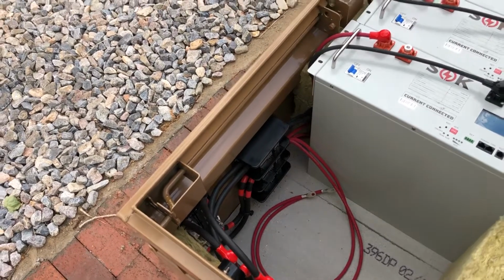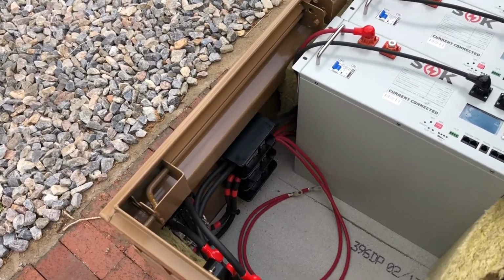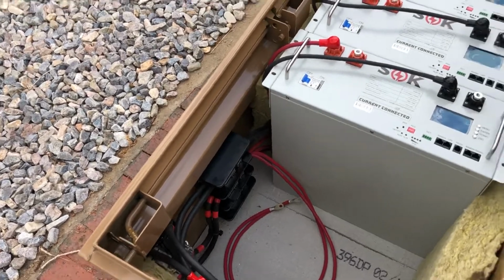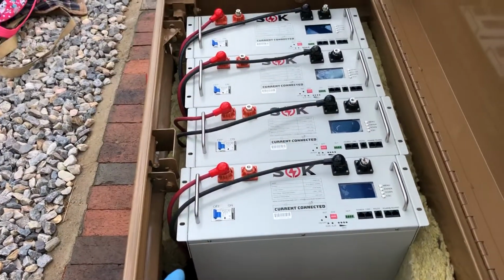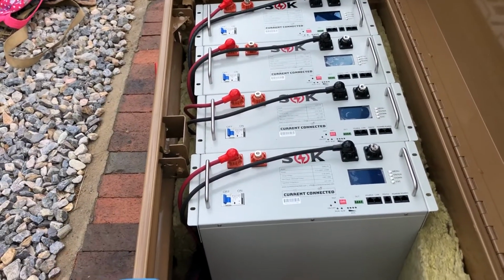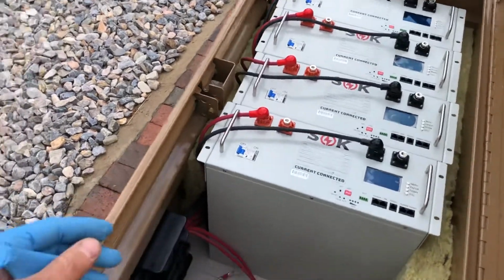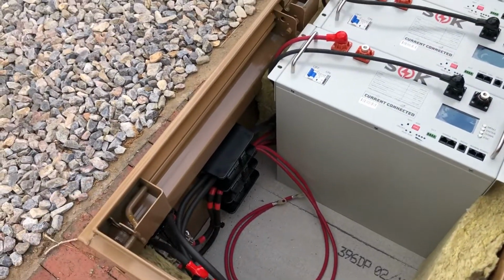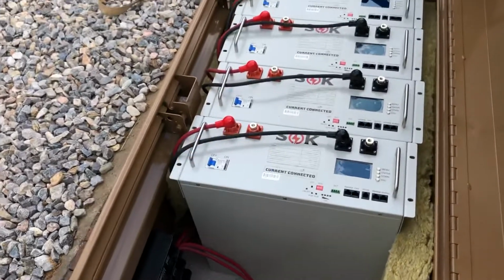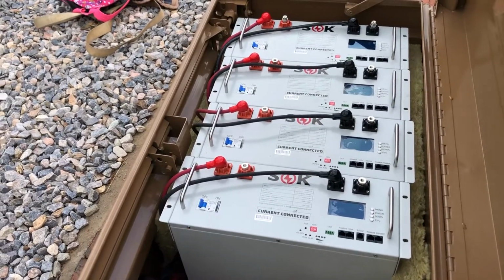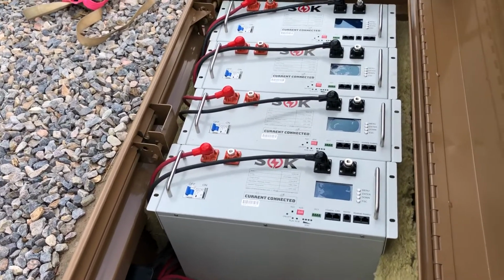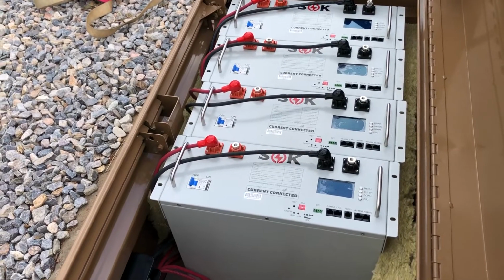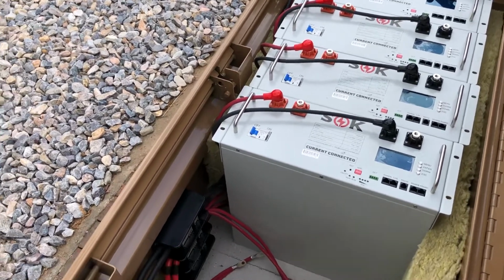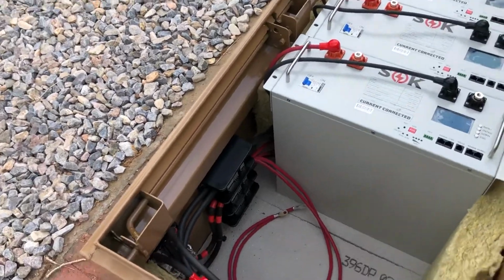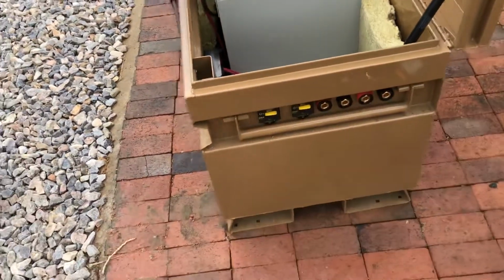The thought I had was 200 is the wrong number for that. Each of these has a capacity of 100 amps each, so even if those were 300 amp fuses, that would still be sized properly for 6 of these batteries. Anyway, I'll think about that and change them if it's a problem.